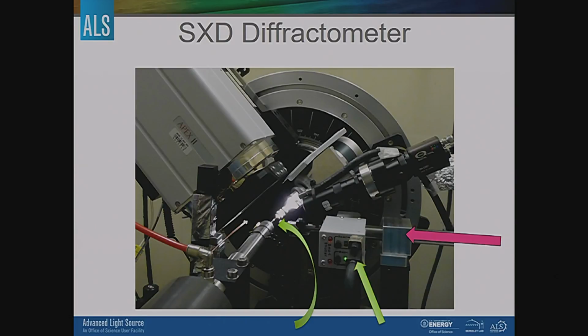Most crystallographic experiments occur at low temperatures. So we're working at liquid nitrogen temperatures, sometimes even liquid helium. In some cases, if you wanted to go really low, you could have a closed cycle cryostat, which would actually be really a box around your sample, and it would be pumped down very, very low. And right in here, if you see that, that is the mount that the crystal is mounted on. That is an X-ray transparent MiTeGen type Kapton loop. So it used to be that everyone mounted their crystals on glass fibers. That's not so much the case anymore. Okay, so that's the general schematic, and of course that's our detector.